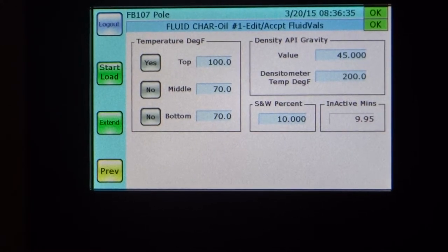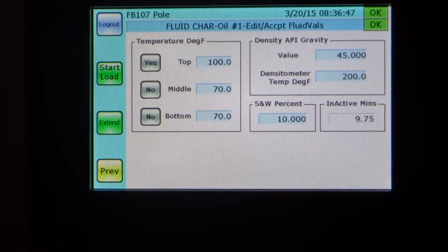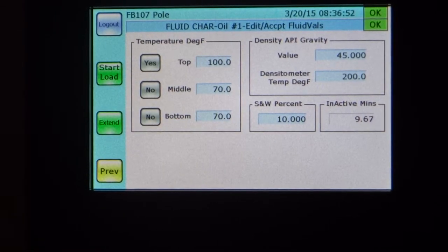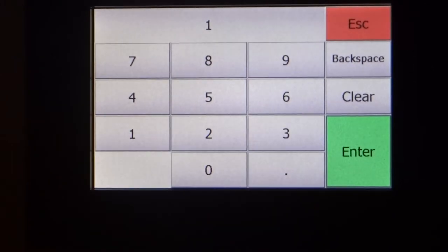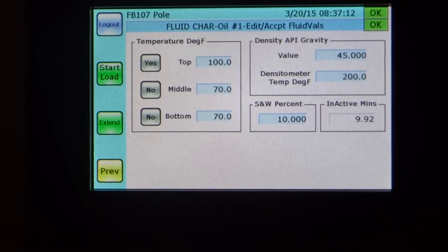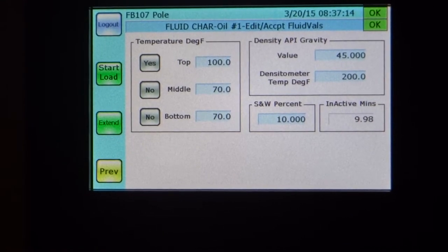At this point, you can begin to enter in various fluid characteristics — gravity, any sort of densitometer readings, temperatures down the tanks. Again, these can all be numbers that are being produced by automation when available. You'll see an S&W percent of 10. Obviously, that's terribly high, but for demo purposes we're leaving it in there because you can actually see some of the difference in the calculations. Normally that may be a number more like one or even less. But I will put it back to the 10 value for our purposes. So we're ready to start a load.